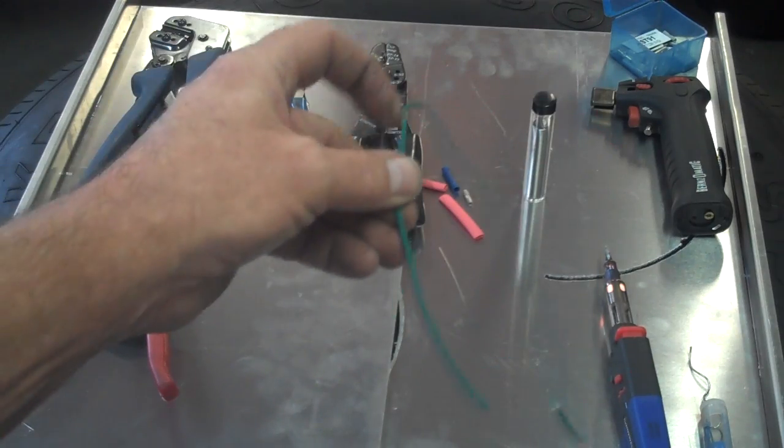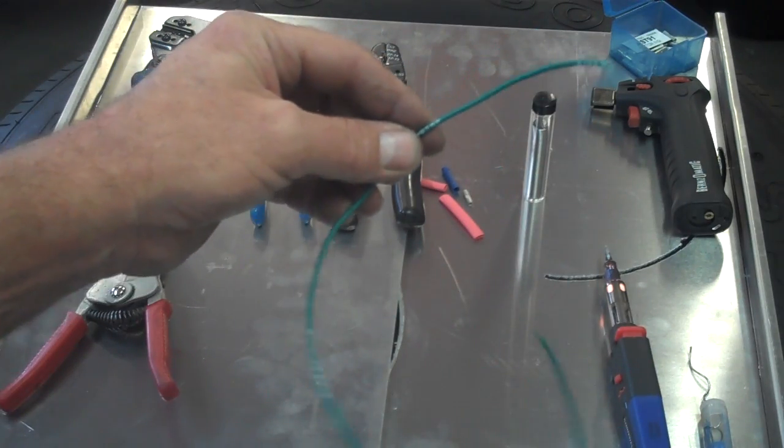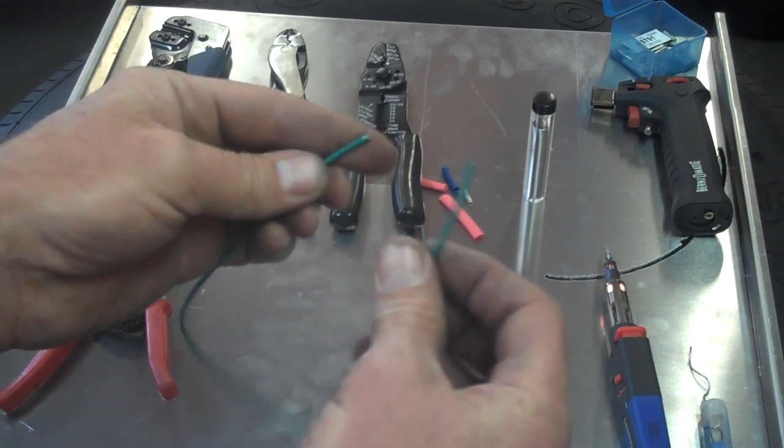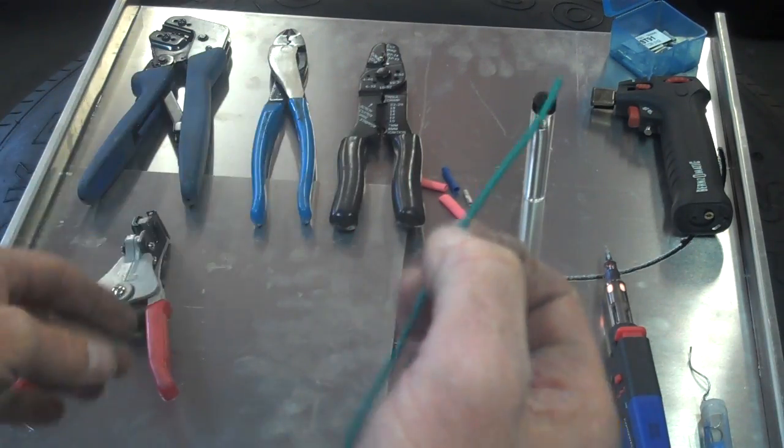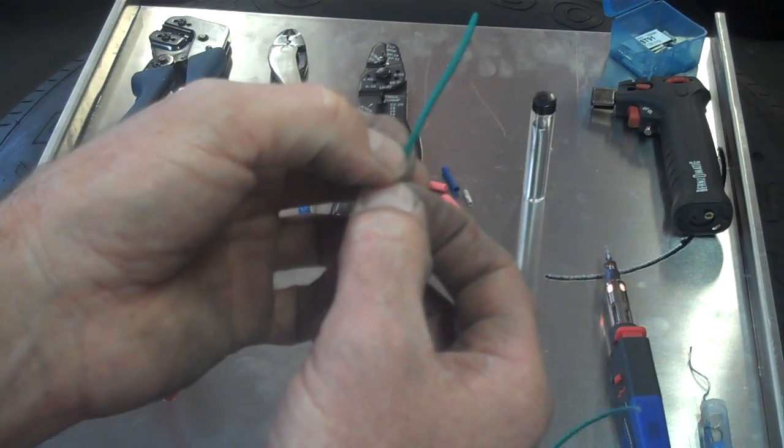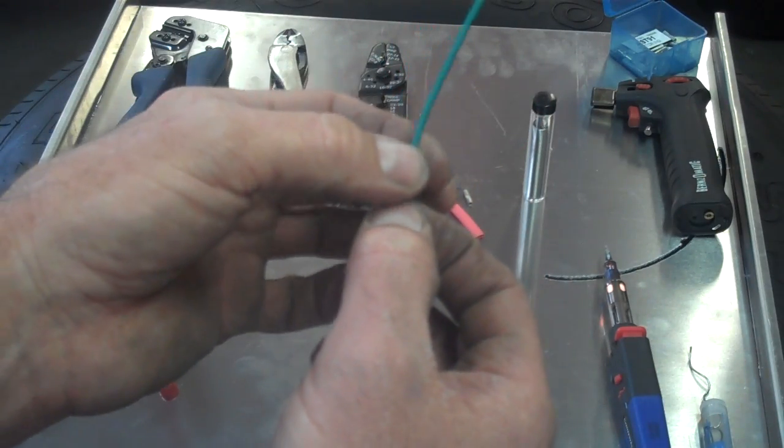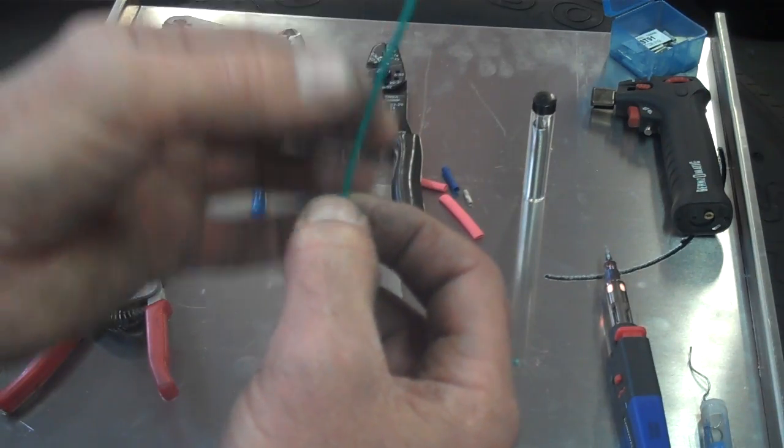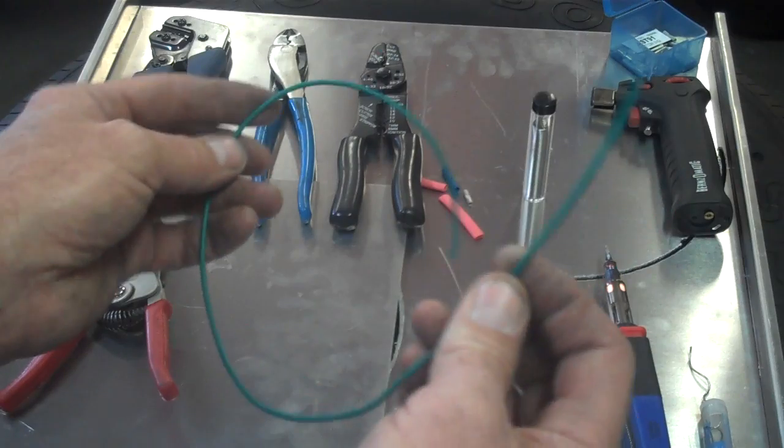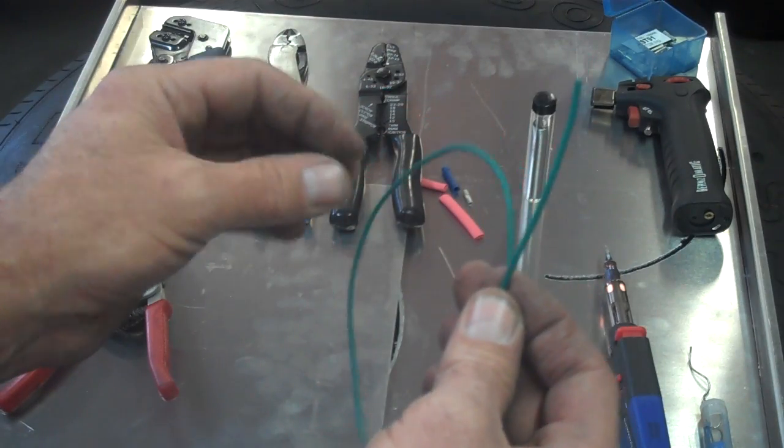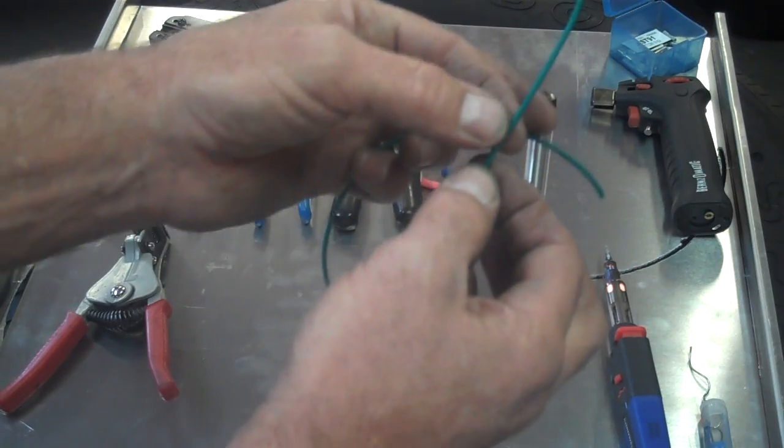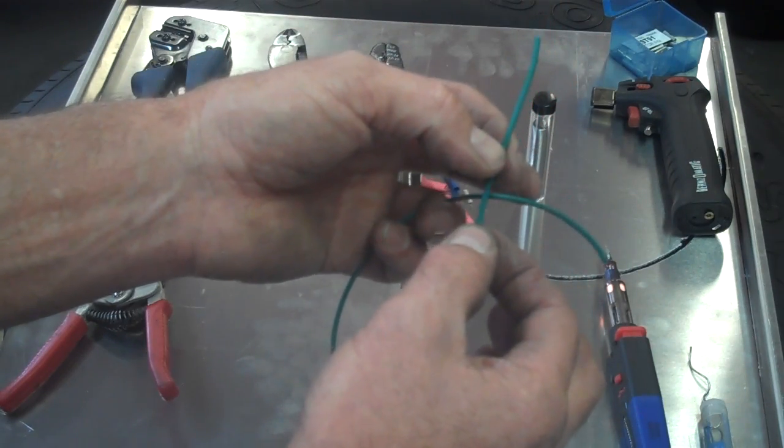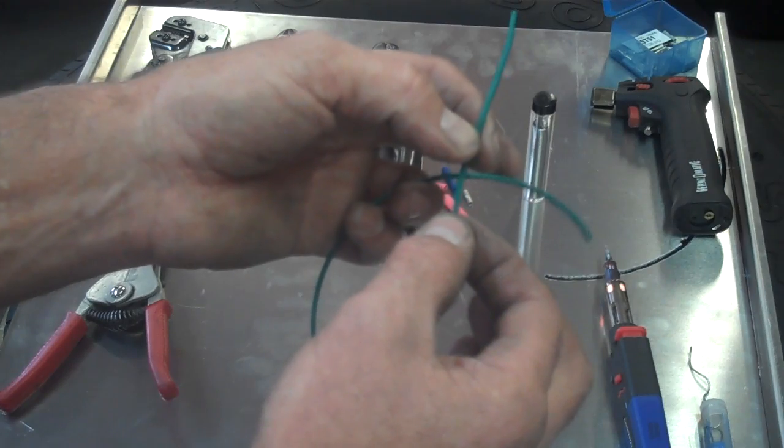Finally, we've got a little bit of wire. It's very important when you're making a connection that you make sure that the gauge of wire that you're using is the same or greater than the gauge of the wire you're replacing. The reason for that is that resistance increases each time that we reduce the diameter of the wire. So if I put a smaller wire in a circuit than what's already there, I'm increasing the resistance in that circuit. We already know we don't want to do that.